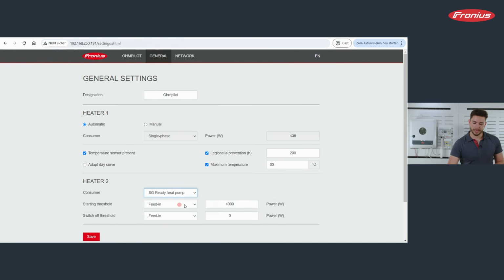Now, SG Ready stands for Smart Grid and allows you to communicate. It's just a 2-pole cable that you connect from the Ohmpilot to your Smart Grid Ready heat pump in order to tell the heat pump, if we have 4 kilowatt of feed-in power, please turn on a higher production, a higher temperature. And if we have 0 watt consumption or feed-in, whatever, please turn off this feature.